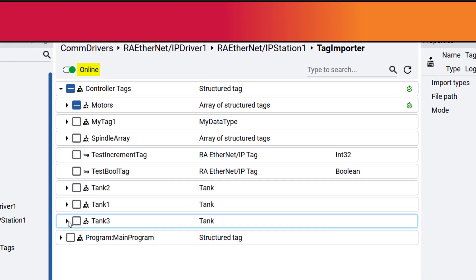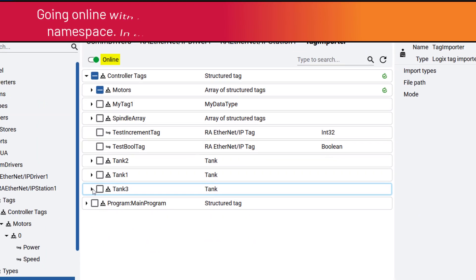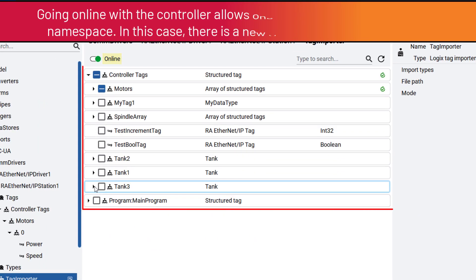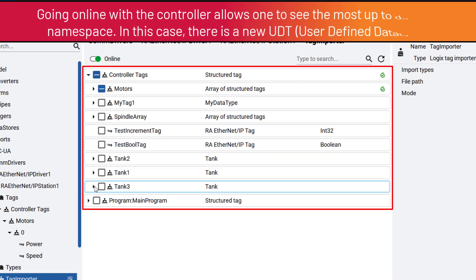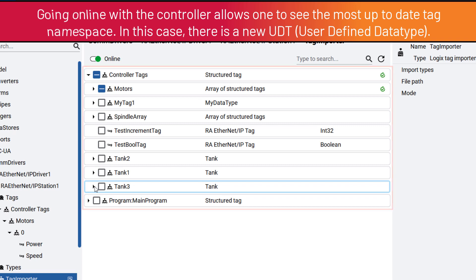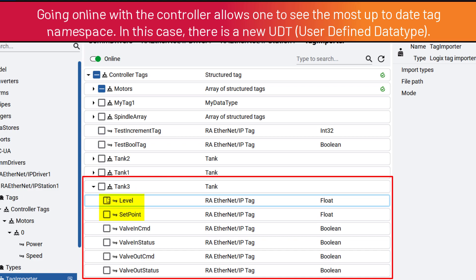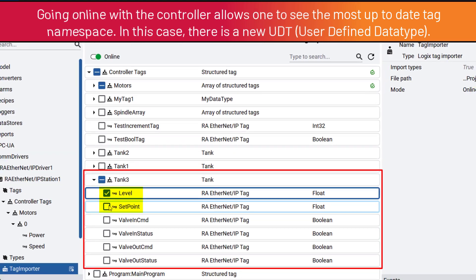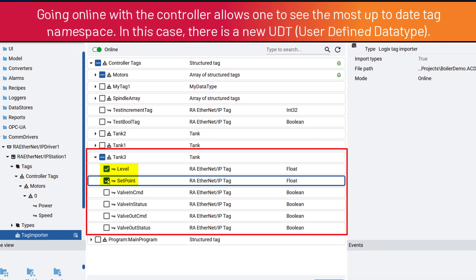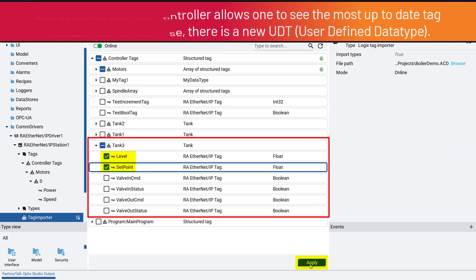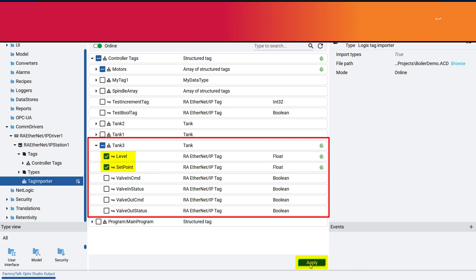The Tag List in the Online Controller program is now different, so we can select additional required tags. Tank 3 is a new UDT that was added online. We can select the Level and Set Point tags of this UDT and after clicking Apply, they will be added to the tag object.